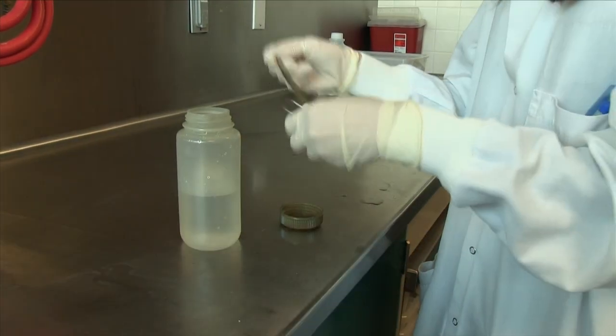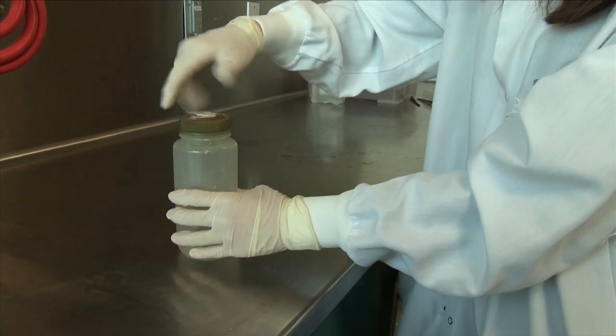There are many cases where different extraction procedures need to be used for these devices in order to test the endpoint of concern. But the FDA wants to make sure that an efficiency is being performed in order to validate that extraction method, to make sure that it is appropriately removing the right amounts of those residuals that are being tested. Now, residuals that are being used for this test have typically been bioburden or protein or TOC or carbohydrates, hemoglobin. The FDA is moving away from bioload reduction. They don't believe that this is a clinically relevant marker to determine cleanliness of the device. However, they do want to see 2 markers at least be used for these device validations.